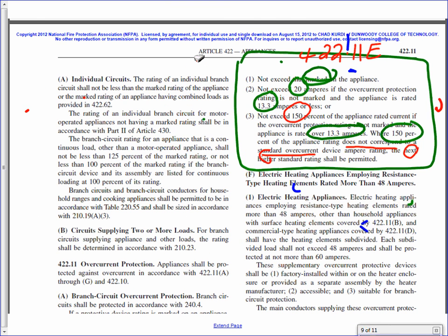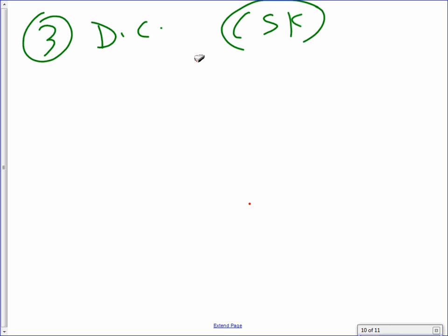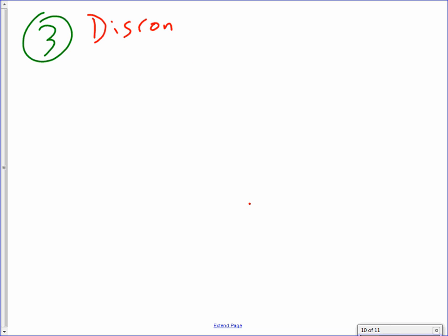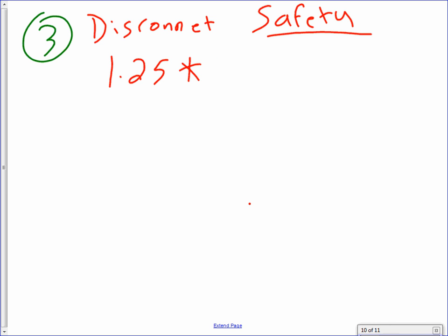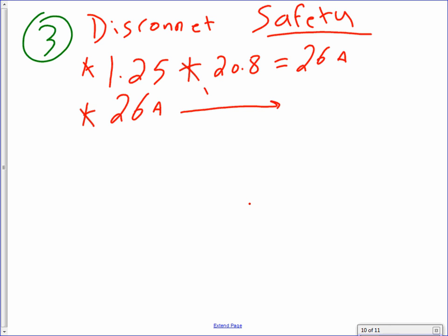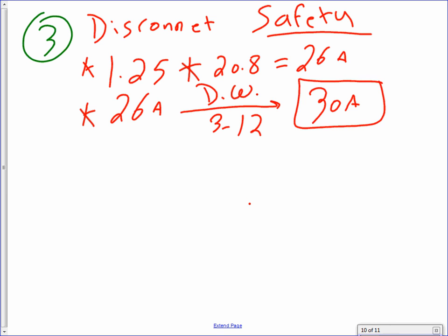The last thing is the disconnect. Guys, why do we use a disconnect? Safety. The way I size the disconnect, I say 1.25, exactly like the conductors, times 20.8. That will give me 26 amps. Take 26 amps to the DW table, 3-12, and it will get you a 30 amp 2-pole disconnect. 30 amp 2-pole, DW is Dewalt from this book right here.